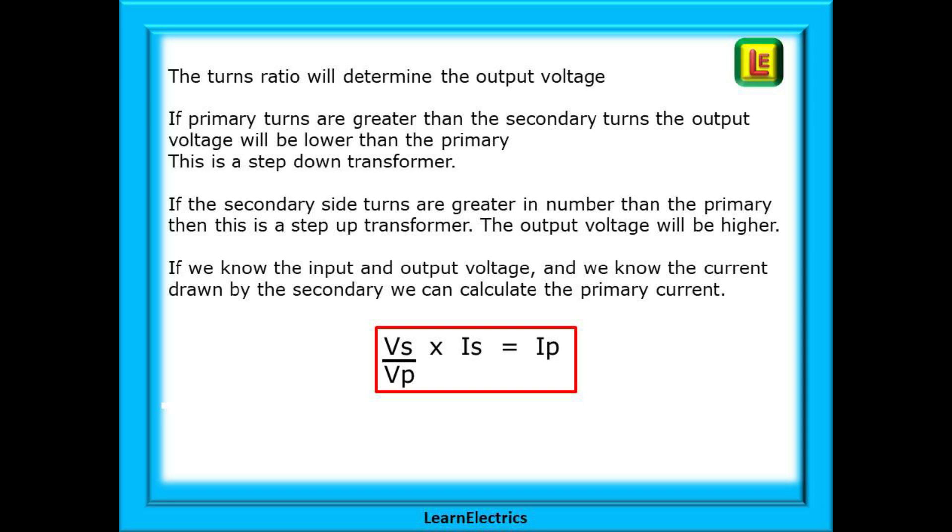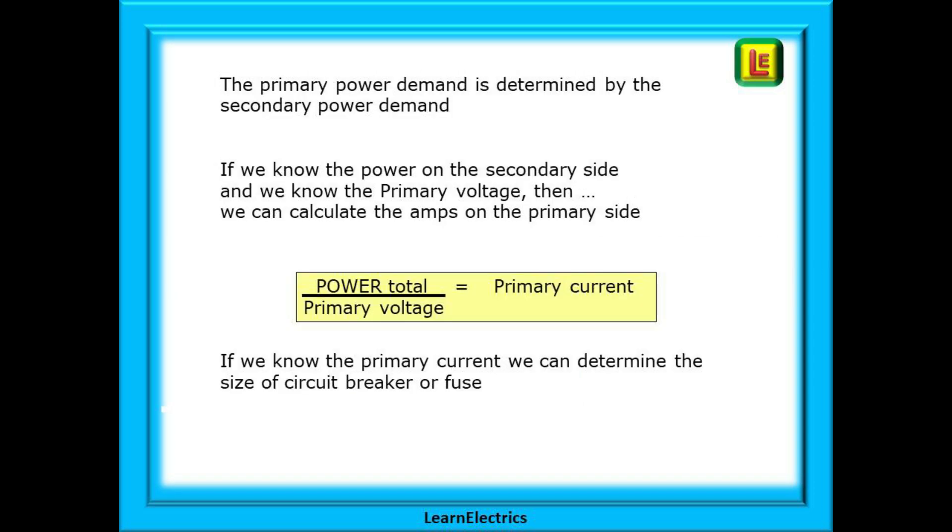If we know the input and output voltage, and we know the current drawn by the secondary, we can calculate the primary current. The primary power demand is determined by the secondary power demand. If we know the power on the secondary side and we know the primary voltage, then we can easily calculate the amps on the primary side. And then, if we know the primary current, we can determine the size of a circuit breaker or fuse.